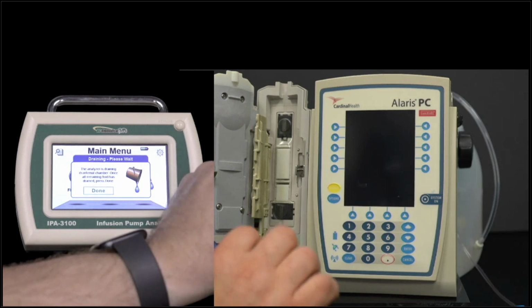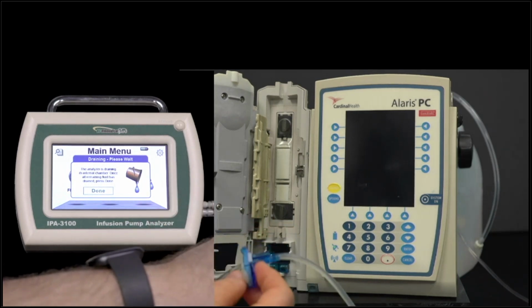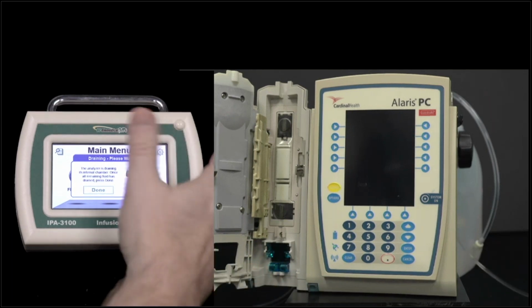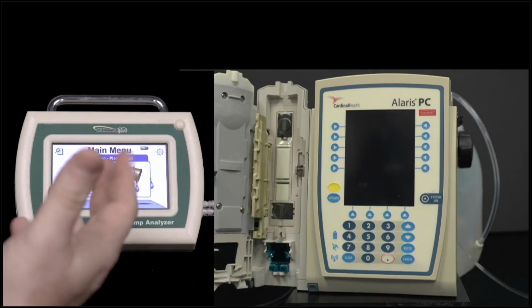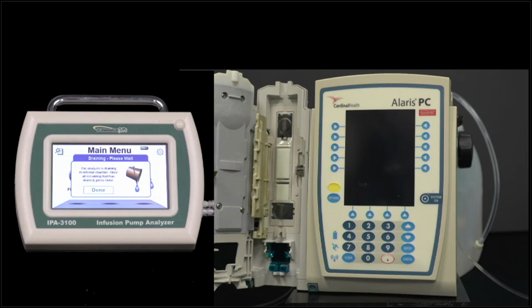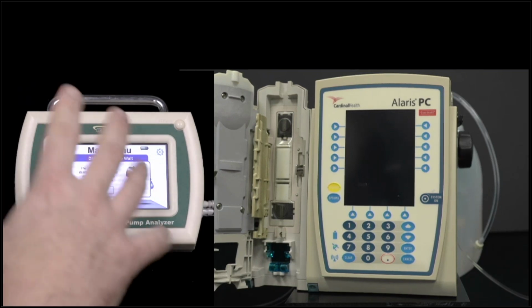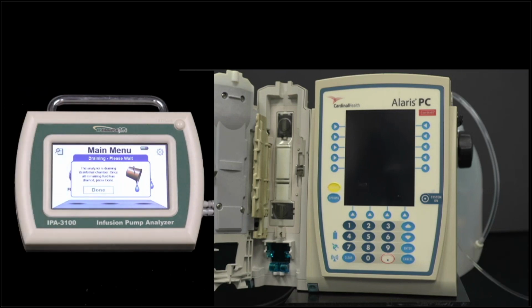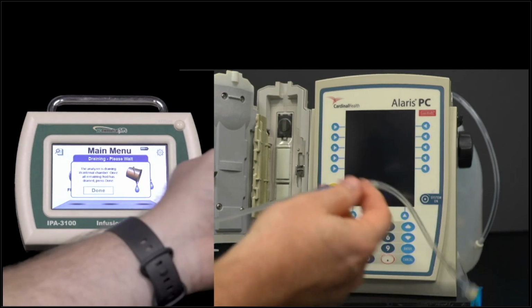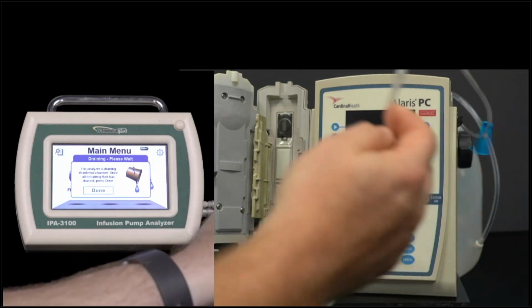Now you might ask, why would we have a drain mode? What's that for? When we disconnect our tubing and we're done testing, let's say we're going to store the unit or send it in for calibration, we would run this drain mode, and that gets all the fluid out of the IPA-3100. But we can tack onto that function and use it to prime our tubing for us, which makes this a little bit easier.